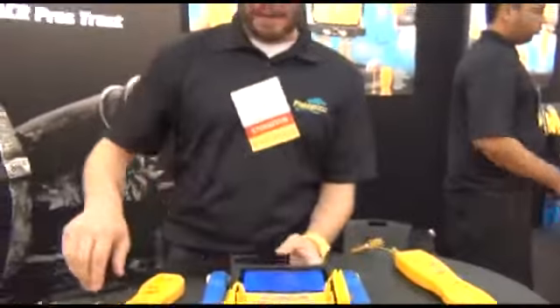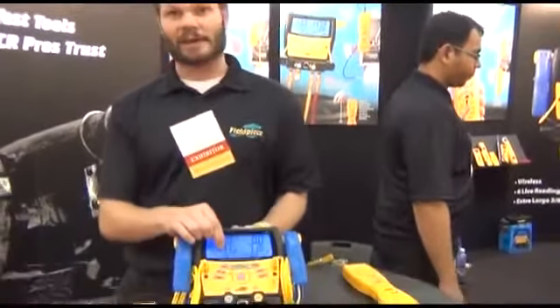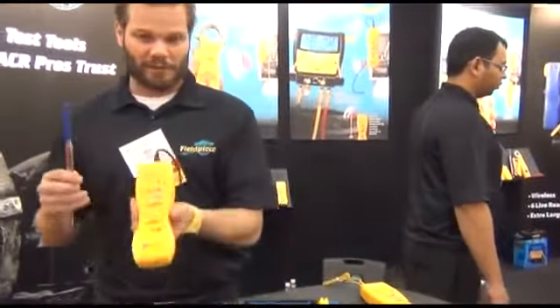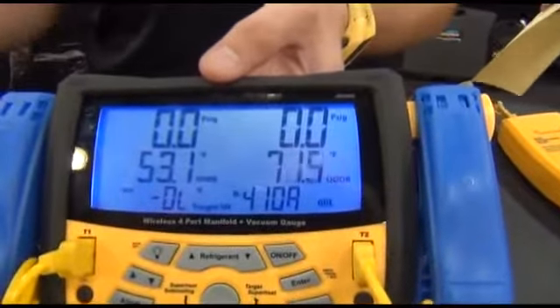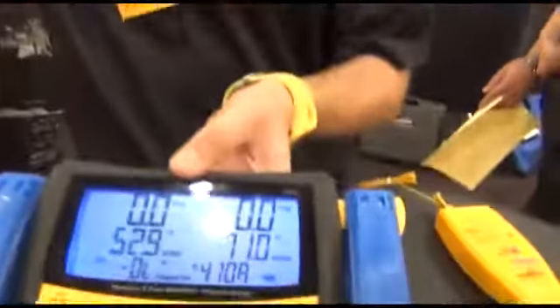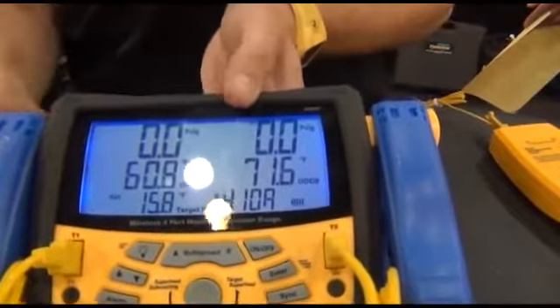Let me show you how the wireless feature works. Basically, what you'll do is you put it into target superheat mode, and you can get the indoor wet bulb and the outdoor dry bulb to calculate your target superheat. This is a transmitter using the normal FieldPiece accessory head that measures wet bulb. This transmits what the measurement is reading to the S-Man 4. Currently on my screen you can see that I have 53-degree wet bulb — that's literally what this wand is reading. I can warm it up and you'll see how quick it goes — went right up to 60-degree wet bulb.